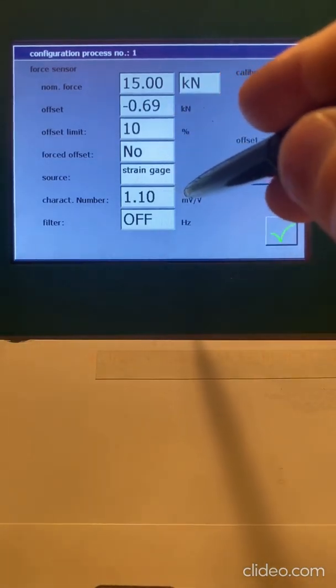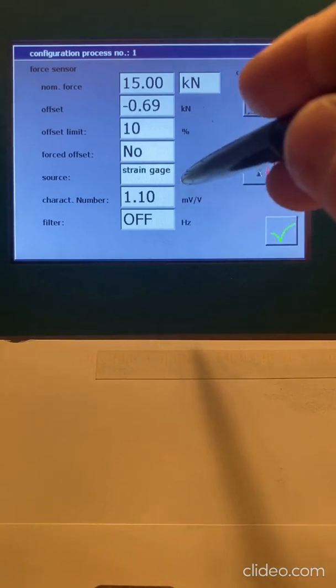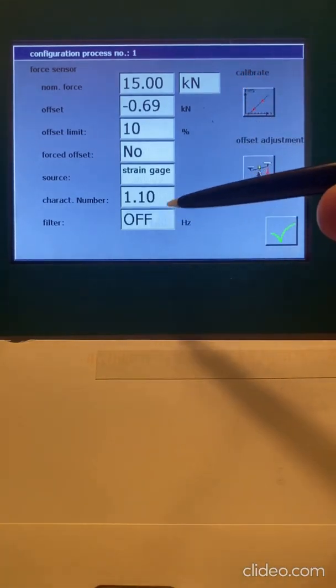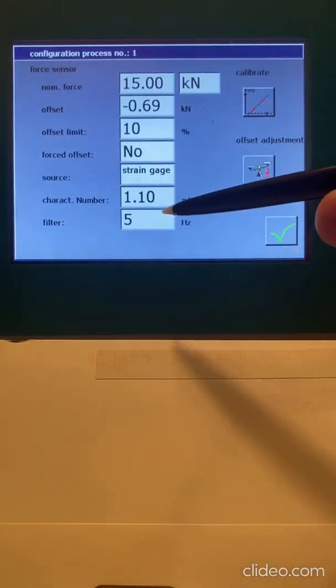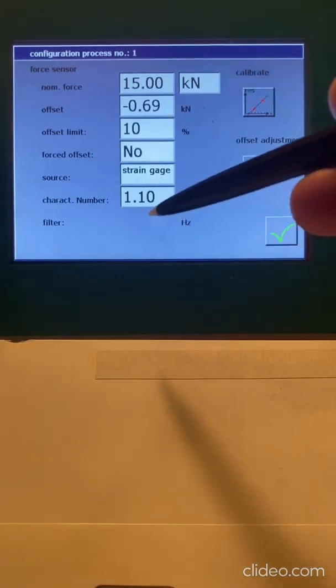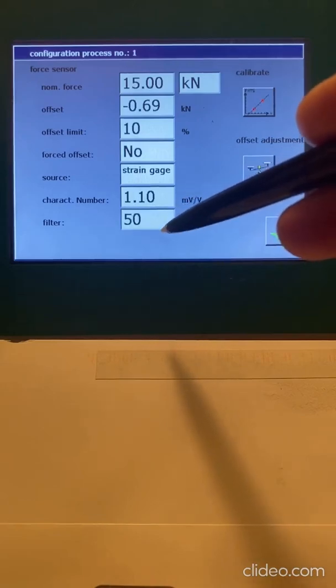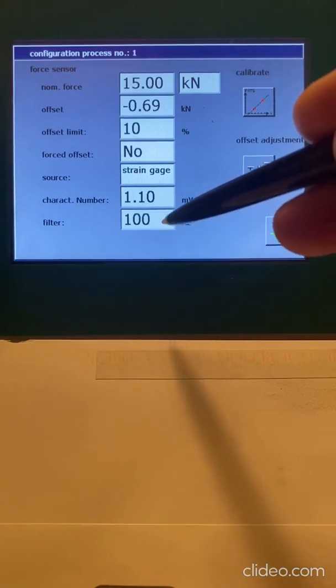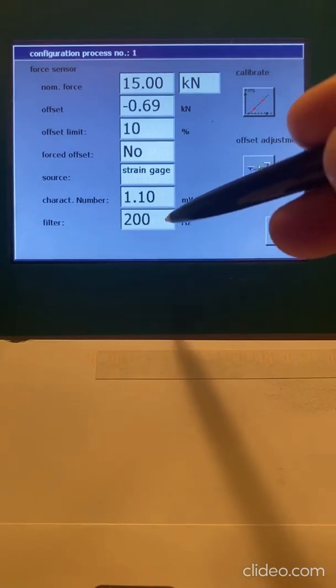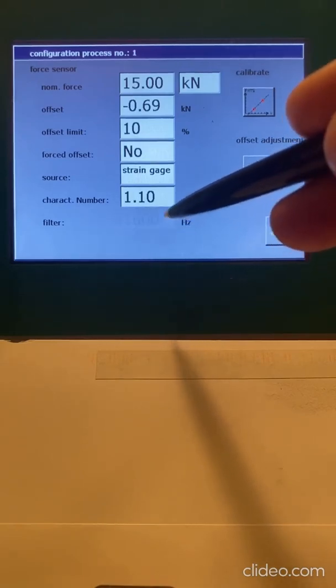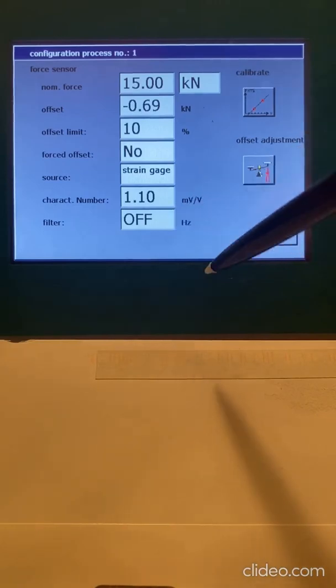Strain gauge, here's my millivolts per volt, if you're using a load cell, and my filter. I can do filter of 5, 10 hertz, 20 hertz, 50, 100, 200, 500, 1,000, or off.